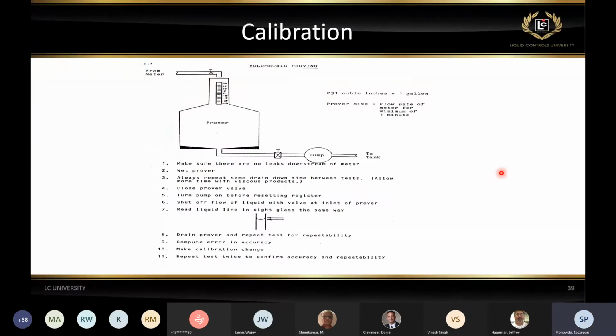Very briefly, since we're approaching 10 o'clock, there are a number of methods of calibration. One of the more common is volumetric proving. That's something that's especially common here in the United States. That may vary depending on where you are in the world. Volumetric proving is fairly simple, but very accurate. You need, again, a prover or a vessel of a known certified volume. So let's say a 100-gallon prover. We're going to be pumping a product through the meter to that prover, filling up the prover, and comparing the volume delivered in the prover to the volume registered on the meter. And then once the volumes are compared, we can go back, calculate our error, and make an adjustment on the calibrator.